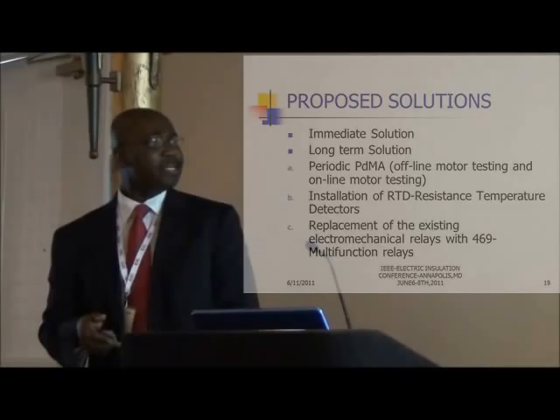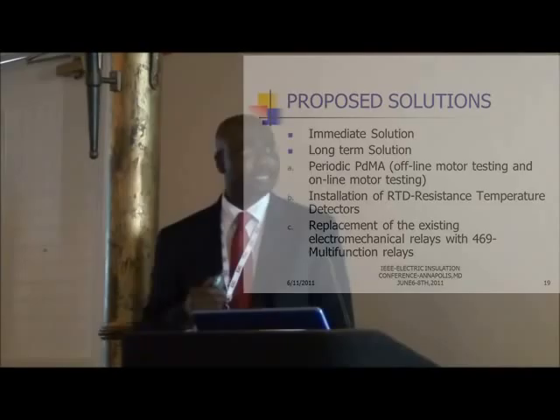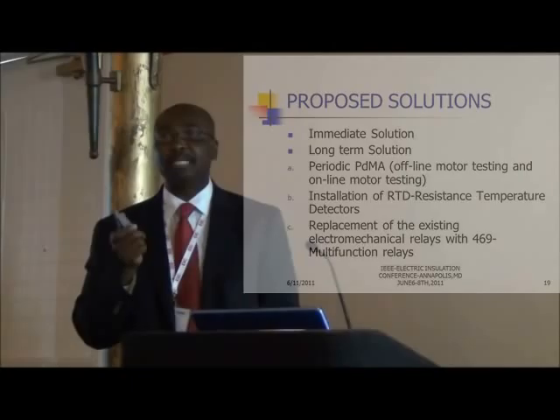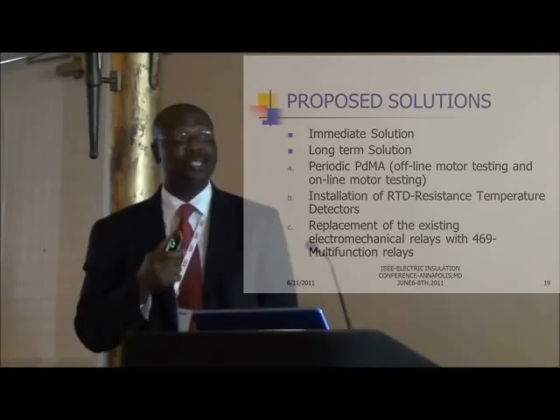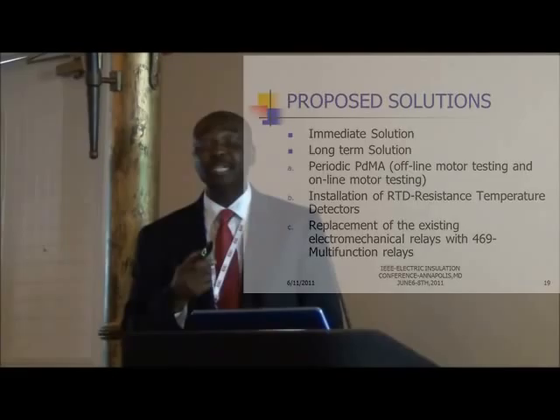Because the failed motor did not have RTDs embedded in the windings, there was no indication to operators that the winding temperature was rising. Typically you have two RTDs per phase. We advised that any motor sent to the motor shop should have RTDs installed in the new windings, so operators can receive early temperature rise indications.